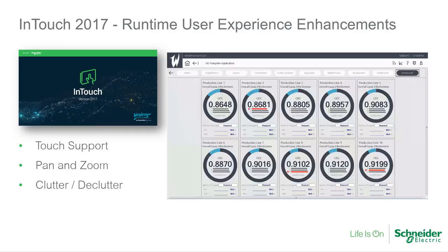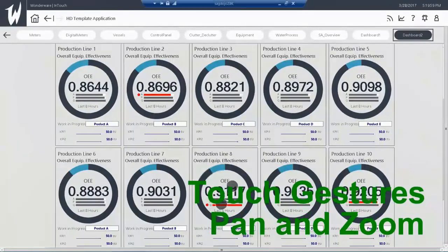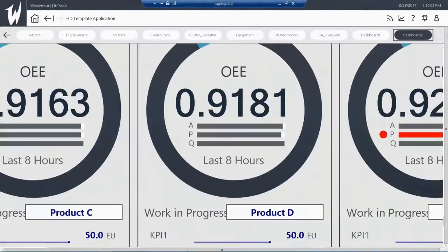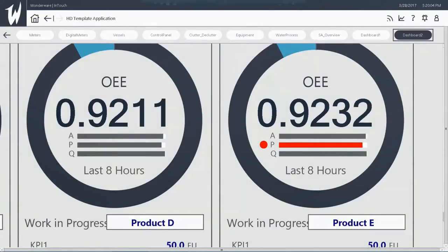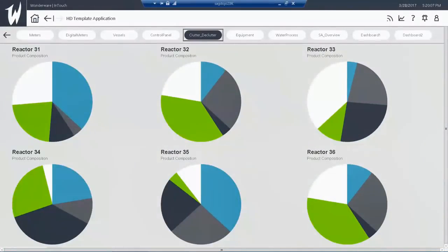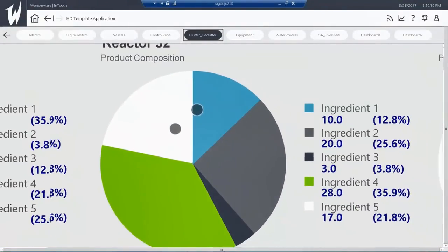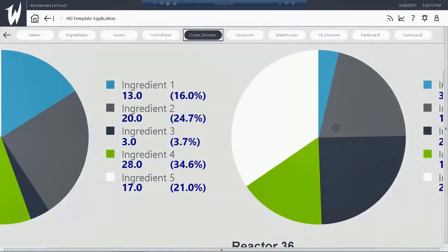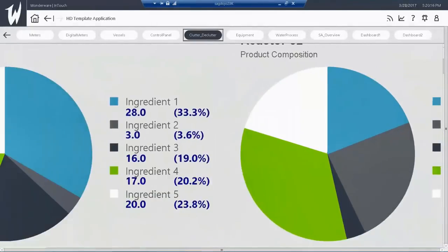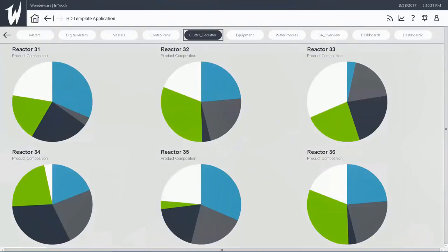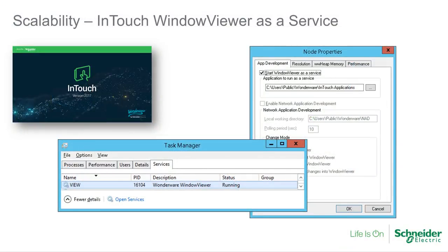InTouch's runtime has gotten several modern upgrades to the user experience as well. We see InTouch now natively supports touch interactions, as well as pan and zoom. Additionally, it supports the concept of clutter and declutter, where the initial view is clean and crisp, but simply by zooming in, the operator can see a new level of details appear. Zooming back out automatically declutters the operator's view. In addition, InTouch 2017's window viewer can be run as a service, allowing operation as a headless data and logic server.